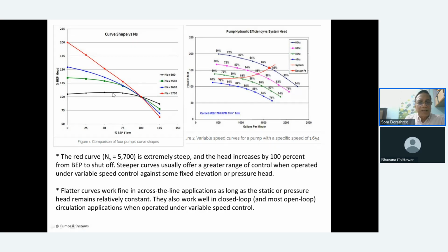This is almost flat. You see, this is percentage of head and percentage of flow. You will find as you go radial, it is almost flat kind of a curve, whereas in terms of axial flow, the head falls very steeply. So this gives you a much better control for flow, because it's falling off very steeply. Whereas here it will be almost the same constant head. You are going to get it here.